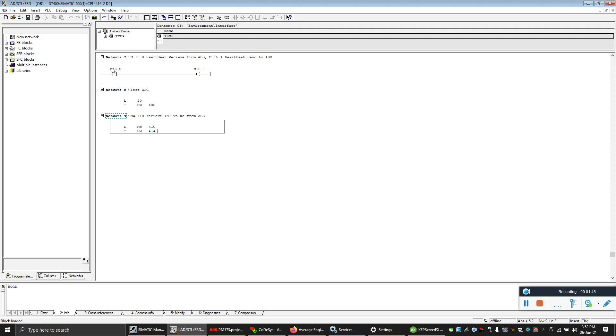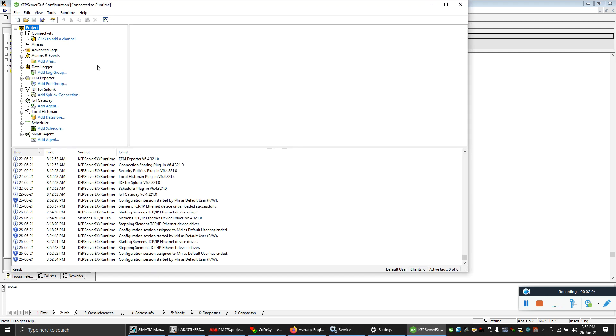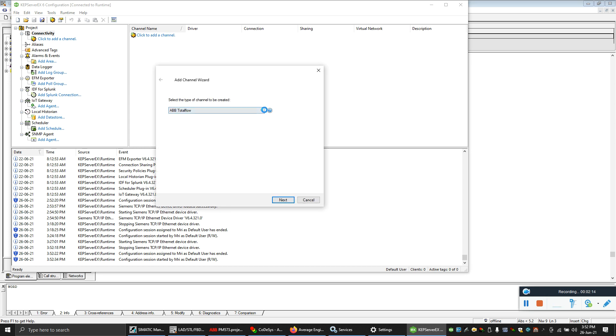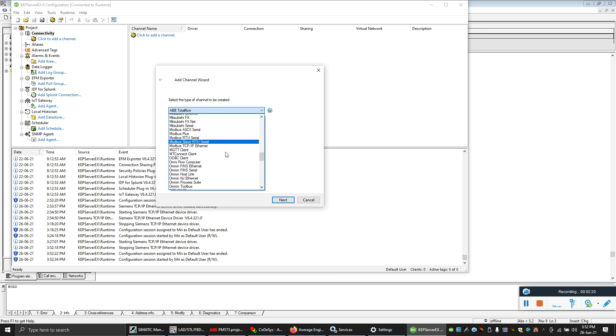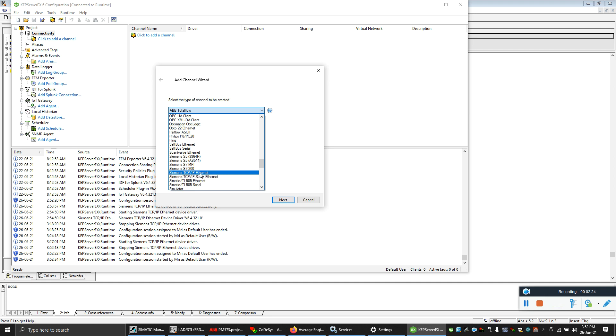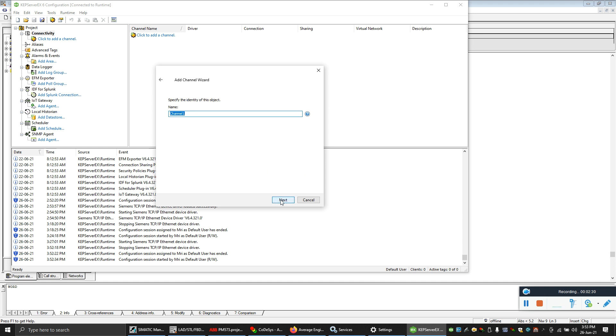I already downloaded this program. Now we need to configure the OPC server for the Siemens S7 PLC. Siemens SIMATIC Manager doesn't come with an OPC server, so I'm using a third-party OPC server called KEPServer. KEPServer can act as an OPC server for Siemens S7 PLCs. First you have to add a channel and select the PLC type — here I'm going to use Siemens TCP/IP Ethernet — then click Next.